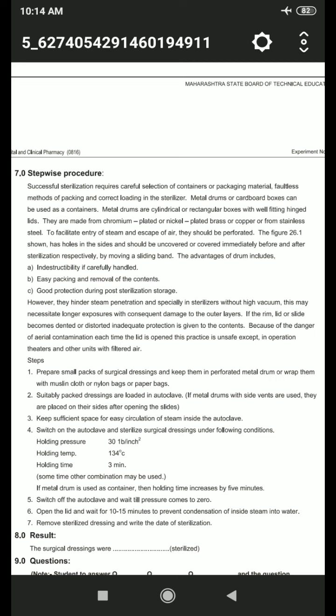Then switch on the autoclave and sterilize surgical dressing under the following conditions. First is holding pressure, that is 30 to 31 pounds per square inch. Then holding temperature is 134 degrees Celsius and holding time is 3 minutes. Then sometimes other combinations may be used. Then, if a metal drum is used as a container, the holding time increases by 5 minutes.